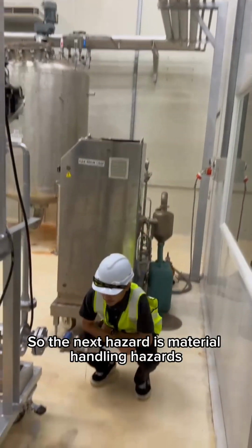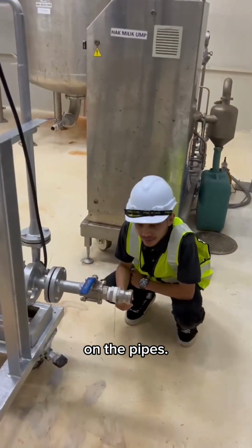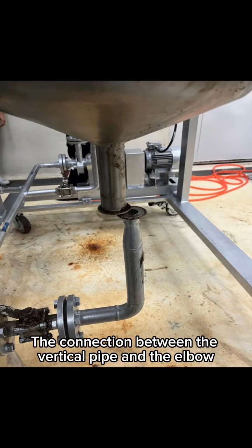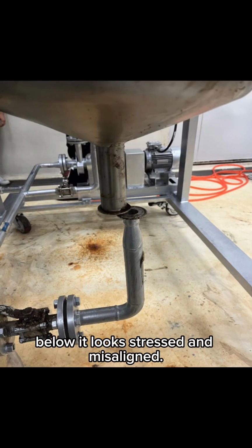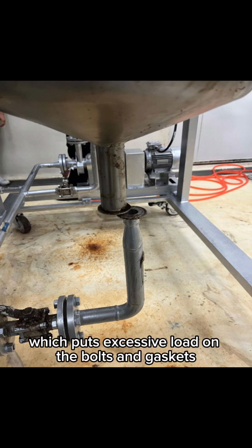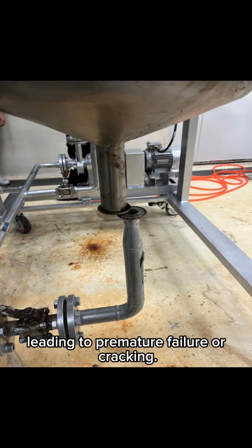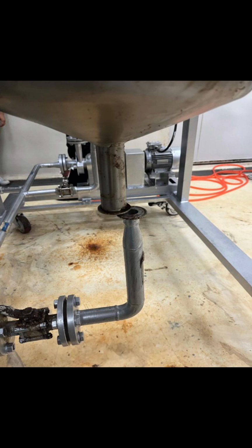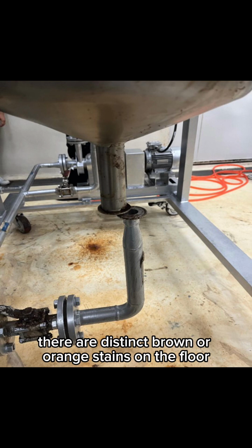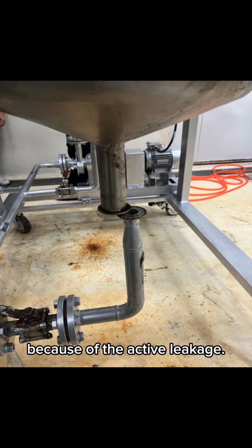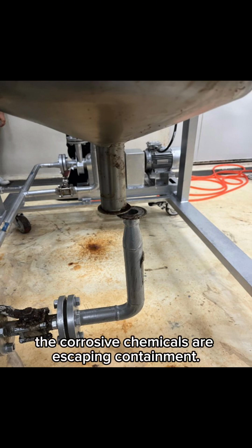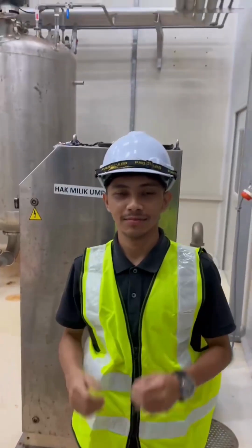The next hazard is material handling hazards on the pipes. The connection between the vertical pipe and the elbow below it looks stressed and misaligned. This creates pipe strain, which puts excessive load on the bolts and gaskets, leading to premature failure or cracking. There are also distinct brown or orange stains on the floor because of the active leakage. This creates a slip hazard and indicates that corrosive chemicals are escaping containment.